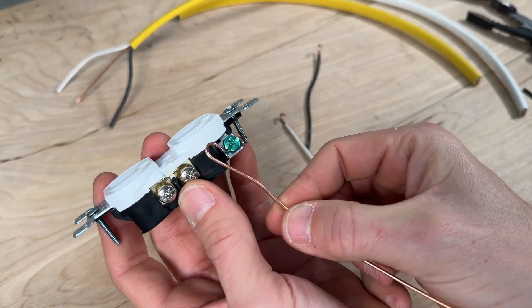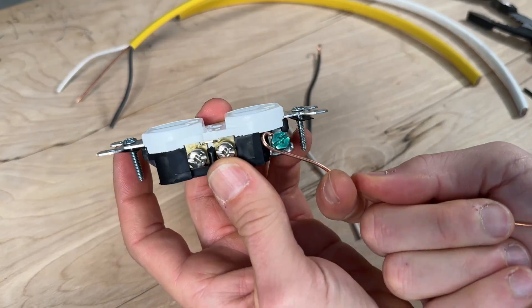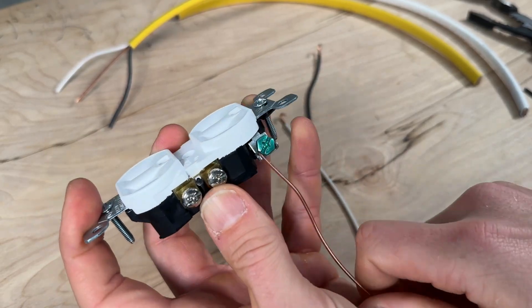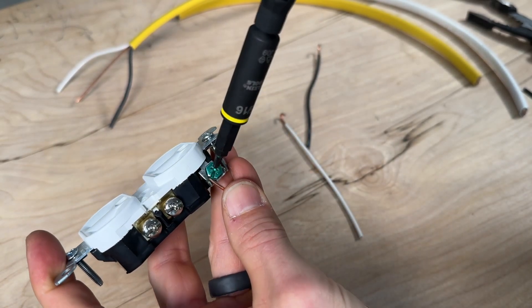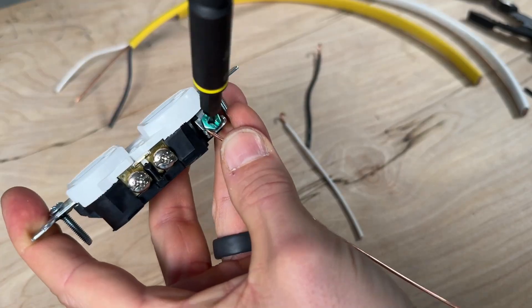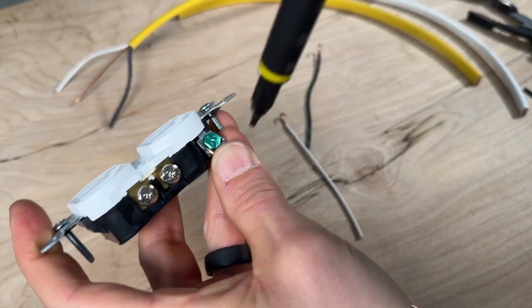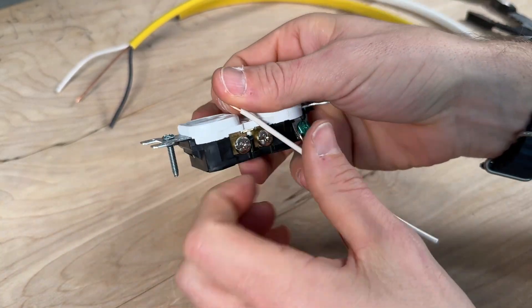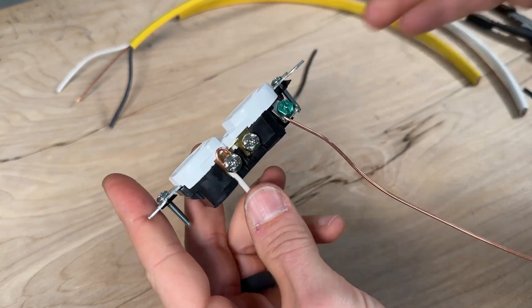Make sure you're going in the clockwise direction starting off with your ground. That is best practice and something I haven't done for many years, so I'm trying to get better at it. Then you'll tighten that down on your bare ground, making sure it's cinched tight to the screw terminal and does not push back out.